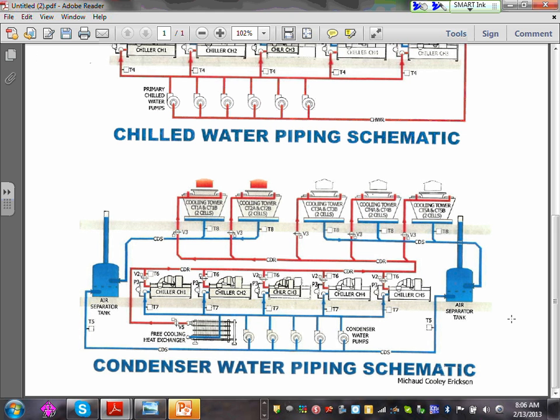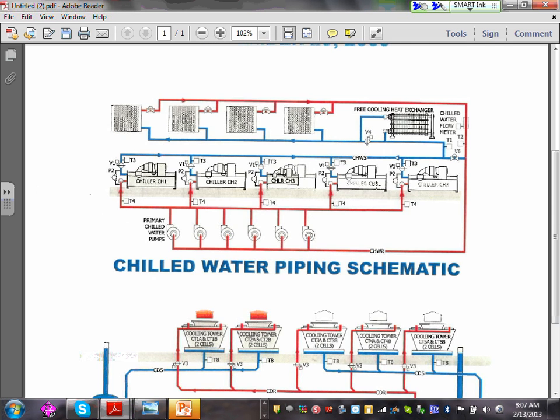They're all tied to the outside cooling towers. They have 1, 2, 3, 4, 5 cooling towers, and they have air separators, tanks to control the water flow and all this stuff. Can you see how it gets complicated, guys? So instead of 1 chiller, they're running 5 in parallel, and that's the outside unit. All these, that's how you chill the water and take it outside and get rid of the heat outside.